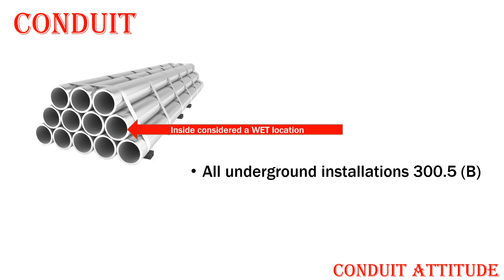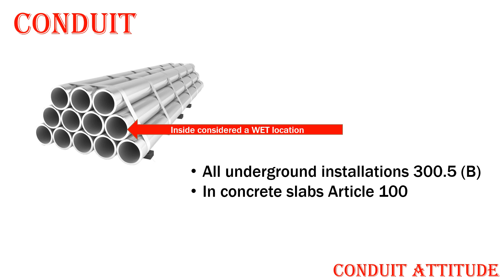The second place I want to talk about is inside of a concrete slab. It took me a minute to find this one in the code book, but you actually have to go back to Article 100, the definition of wet location, and it specifically mentions concrete slab by name. So inside of a concrete slab, wet location rules apply.